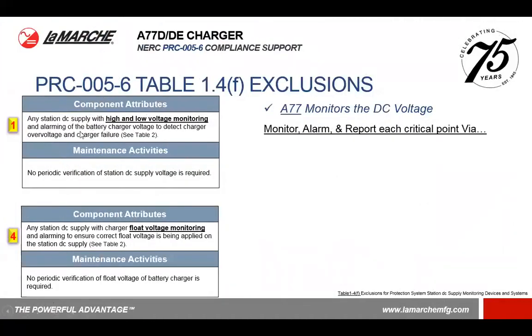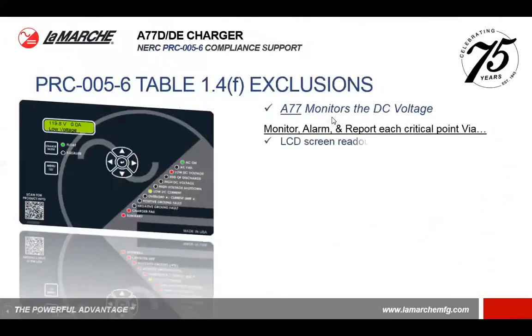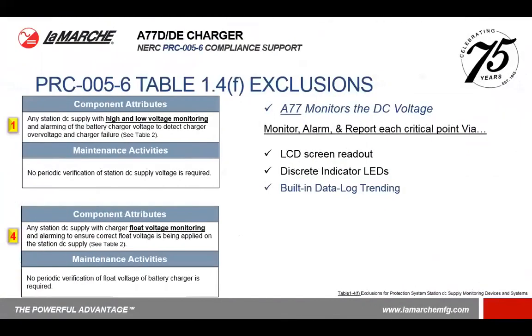Let's look at attribute 1 and 4. Attribute 1 is high and low voltage monitoring, and 4 is float voltage monitoring. Well, the A77 monitors for the DC voltage. Let's take a look at what the voltage is now. You can tell what it is on the screen, and you can observe any alarm indications directly on the discrete LED indications. But that only explains what it is now. How about where has it been? So for high-low monitoring and the float voltage monitoring, we also have built-in data log and trending in the charger itself.